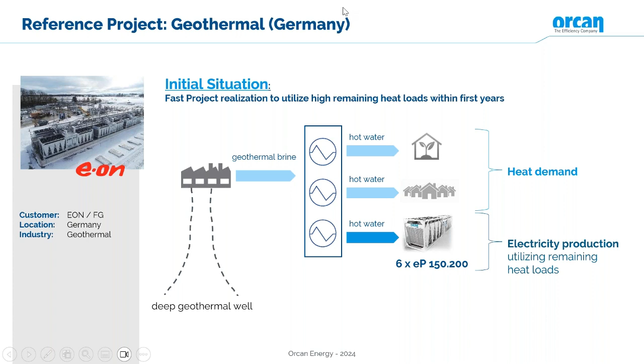Initially we installed 6 units of our EP150-200, with a net power output of about 640 kilowatts electrical. Later, more heat was required for heating the greenhouses than for the district heating system, and there simply wasn't enough heat available for all 6 units anymore. So we decided together with the client to remove 3 of our ORCs. Today, if you visited the plant, you would see only 3 units left.